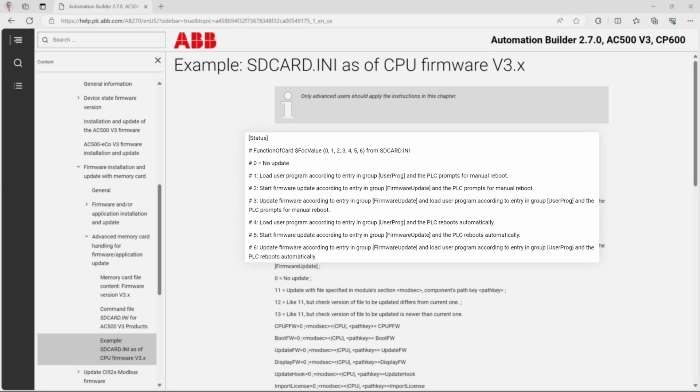Values 4, 5, and 6 of function of card parameter will tell PLC to perform the same operation as it was with 1, 2, and 3. But in addition, at the end of the process PLC will reboot automatically.